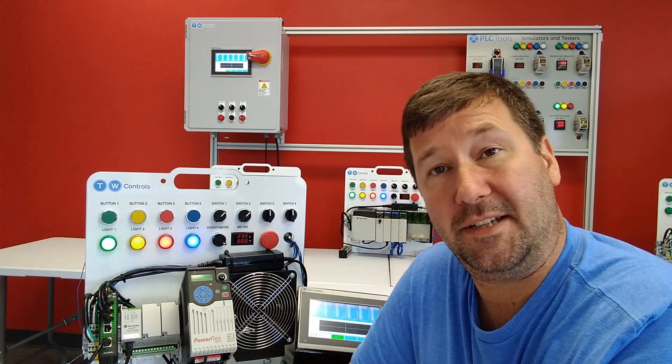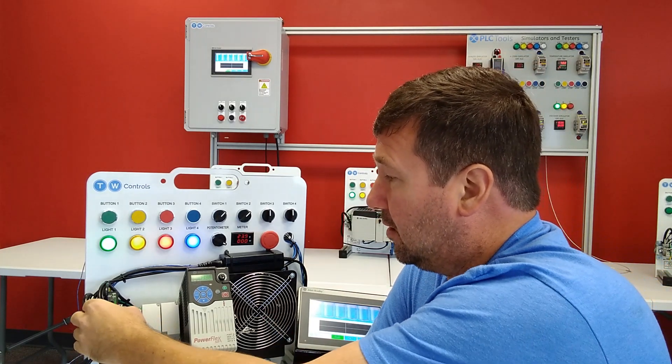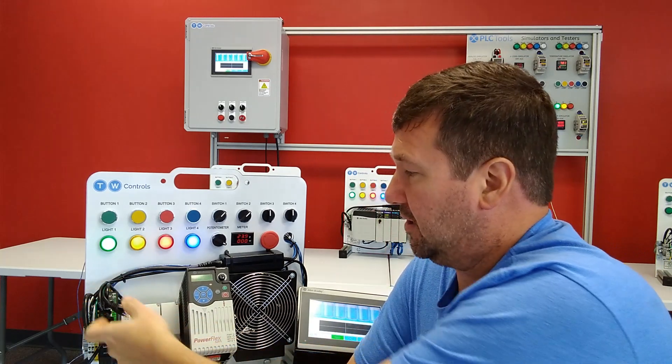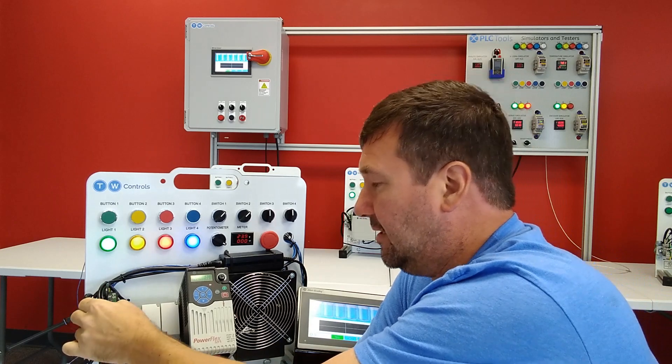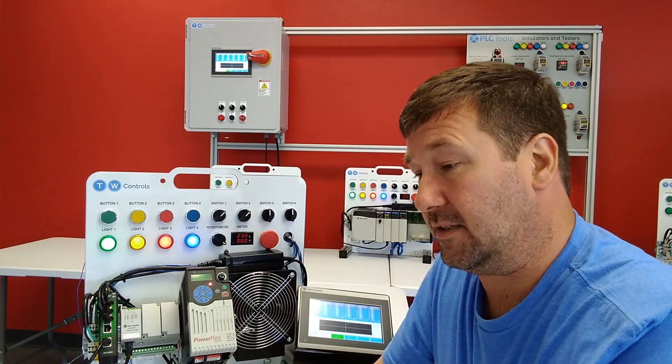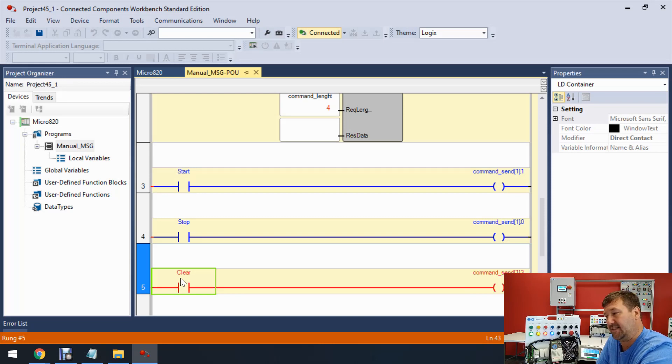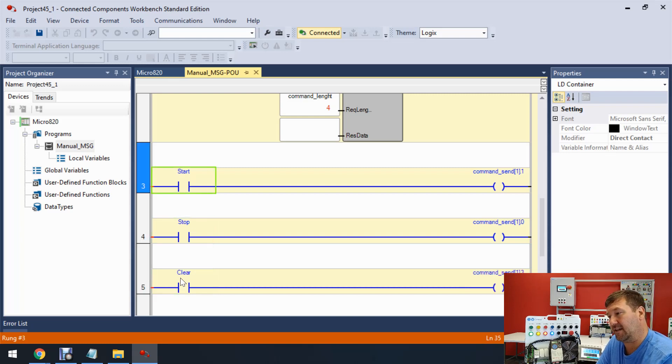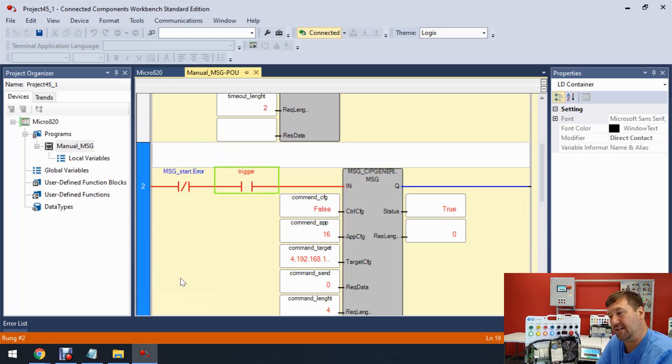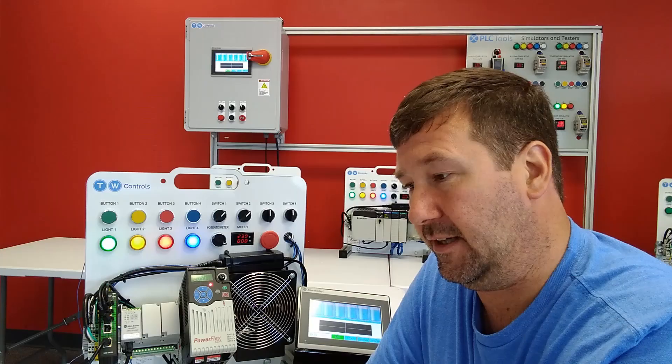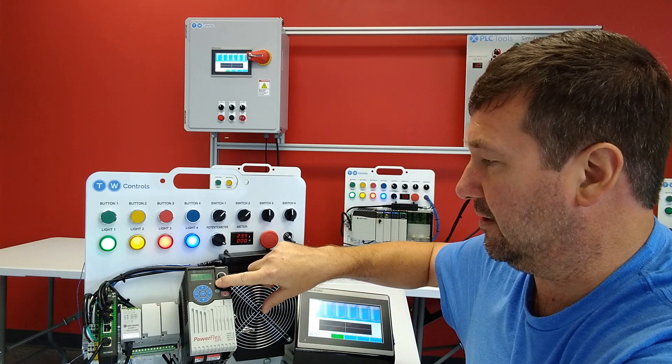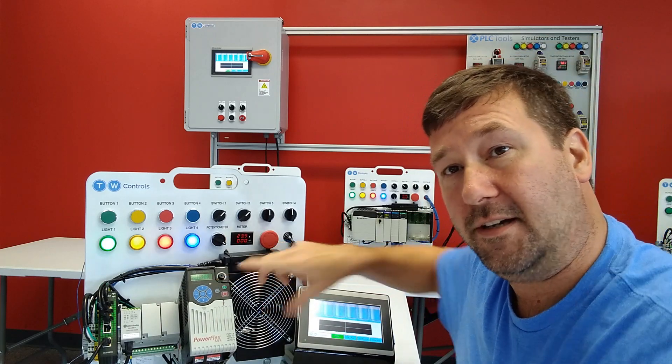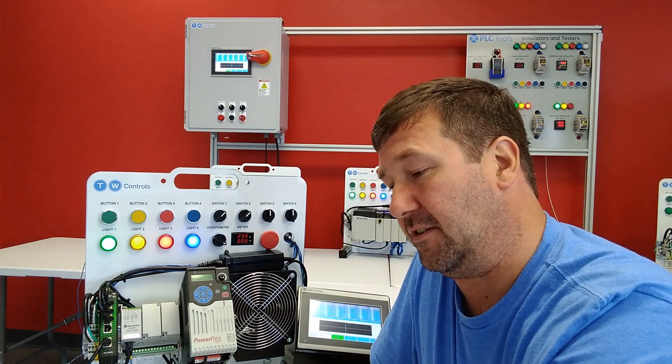But if we unplug our drive, which is going to give us that same Ethernet loss. And now we plug it back in. So we think everything is fixed. And we toggle this clear bit. It's not actually going to do anything. And that's because you have to get this Ethernet communications going again. So we need to toggle the trigger bit off and then toggle it back on. And now we can come down to the clear and you can see the red flashing light when I toggle this. It goes out. And so that is how you would clear the reset on the drive.